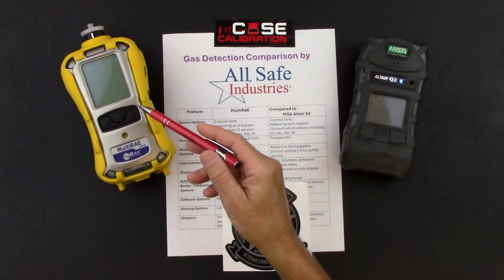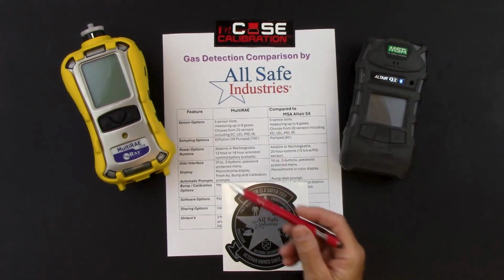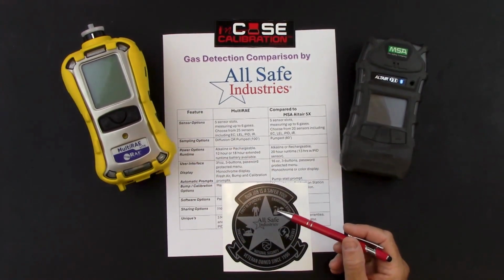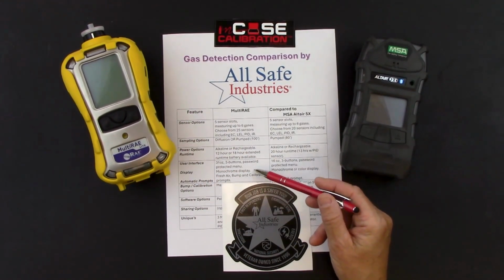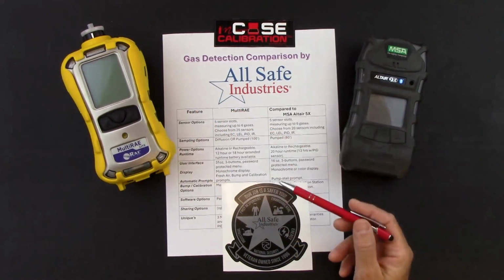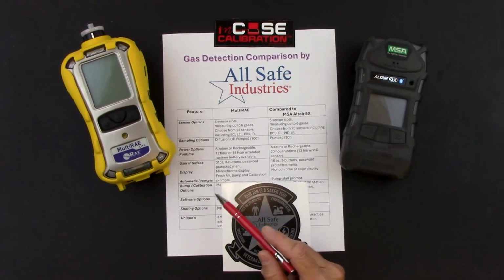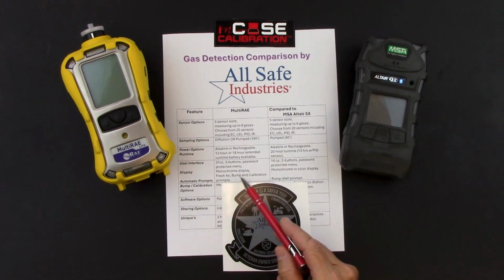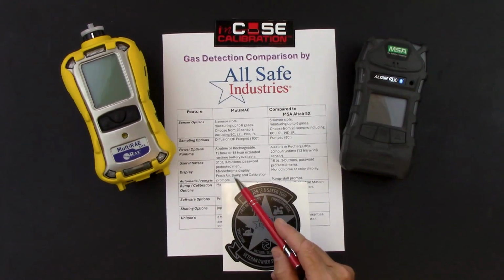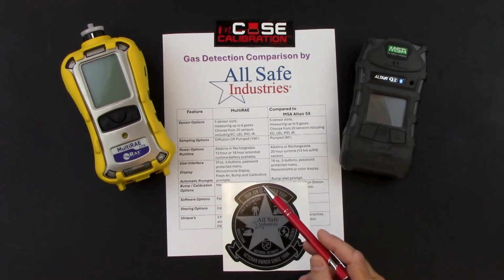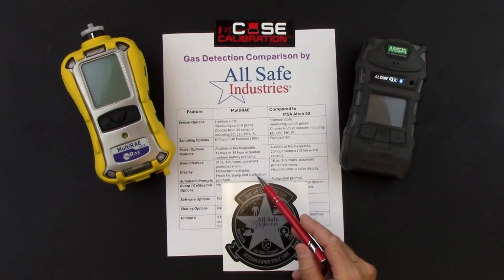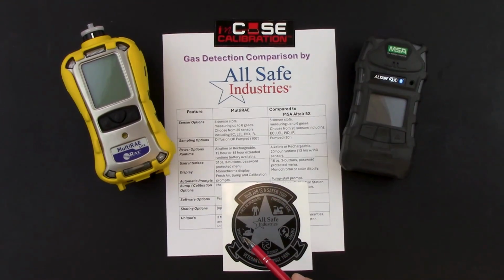We can also password protect the MultiRAE so that only people that have been trained can get in and make changes to your instrument. It has a monochrome display that we'll see here in just a second when we power up. And then we can program a few different automatic prompts on a MultiRAE. We can have it prompt for a fresh air calibration, a bump check, or a full calibration using our calibration gas.